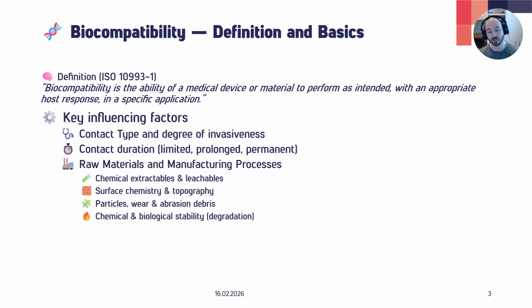And this is exactly what I mean when I say, hey, can we use recycled materials in medical devices? Well, it depends. In a permanent implant, it's probably not that good of an idea because the biocompatibility risk is certainly very, very high, since you have a very long and very invasive application. And if you have something like a crutch, you have contact with skin, or even no patient contact because it's only the mechanical parts. In that case, the ISO 10993 might not even be applicable since you have no patient contact, or it's a much lower risk.